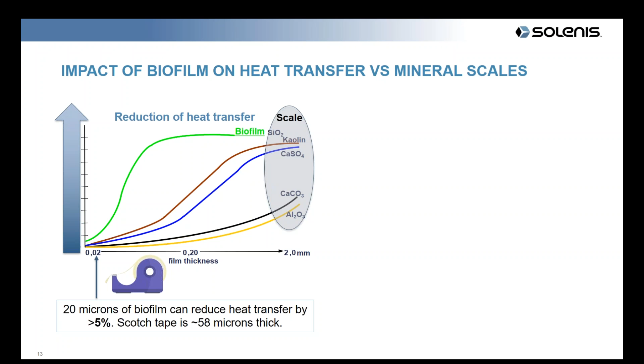Scale deposits are really visible, and you can see those, so you normally know you need some hydroblasting or acid cleaning to remove them. So when you open up your heat exchanger and there's no scale, you think everything must be okay with my water. But in fact, you don't necessarily see a biofilm when you open it up, and that could be even more insulating than the hard scale.